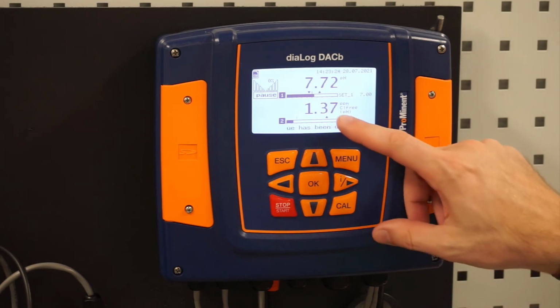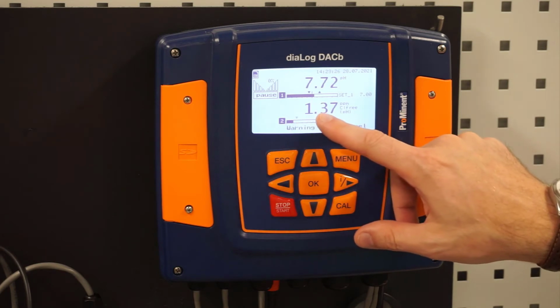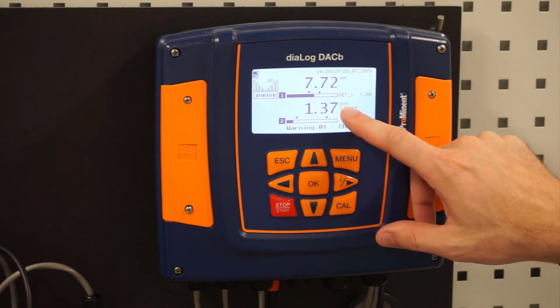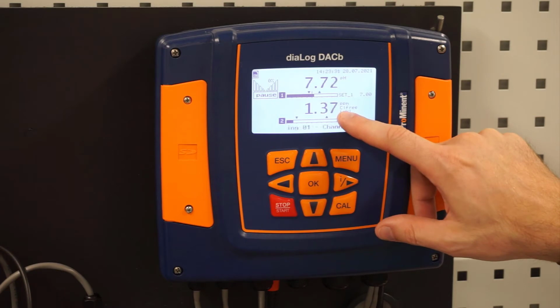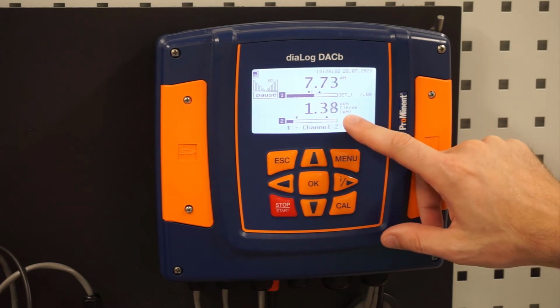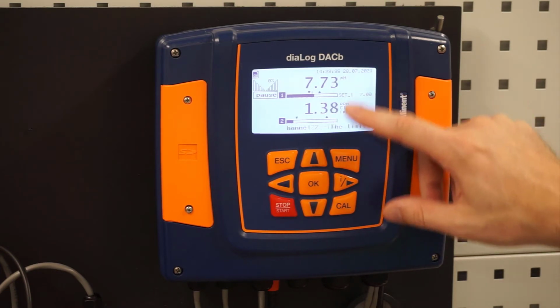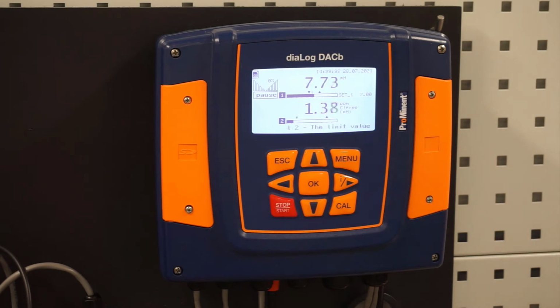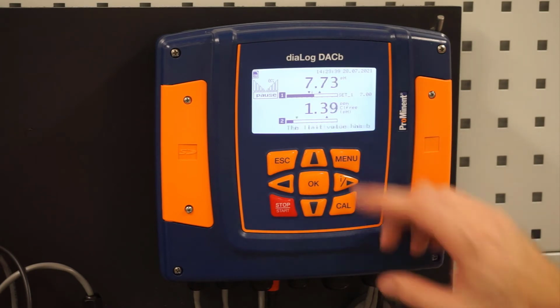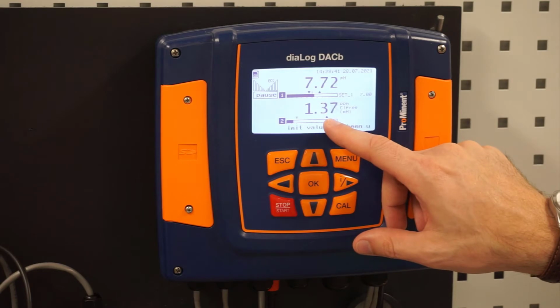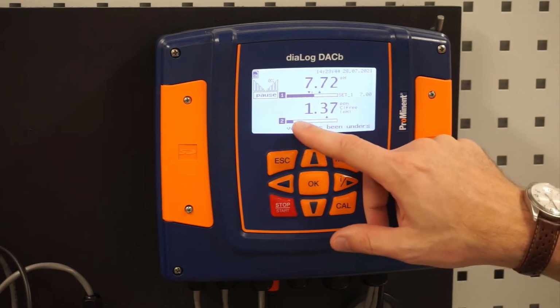Same thing down here on channel 2, that is our free chlorine. You can see it's measuring in ppm, chlorine free, and then we are using our pH sensor to compensate our free chlorine reading. And then under that you can see we have our high limit, low limit.